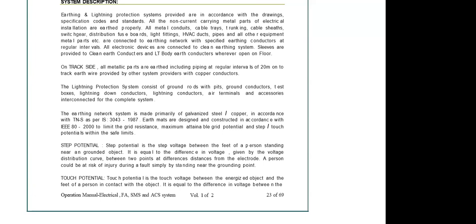And touch potential is what? It is the touch voltage between the energized object and the feet of a person in contact with the object. Like last time I was discussing, if you are in an open area where there is rain happening and you go into a shaded area, while entering from the rain area to the shaded area, again there is a difference in voltage. So these two need to be addressed during designing the earthing system.